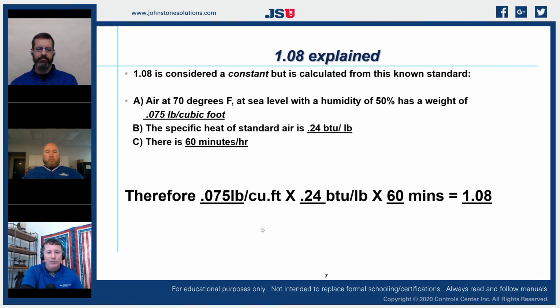So if we take that 0.075 pounds per cubic foot, we multiply that times 0.24 BTUs per pound times 60 minutes, so we can get it up to an hour. That now gives us a correction factor of 1.08. So if any of those numbers change, if our temperature is different, if our humidity is different, if our pressure is different, it changes all of that calculation.